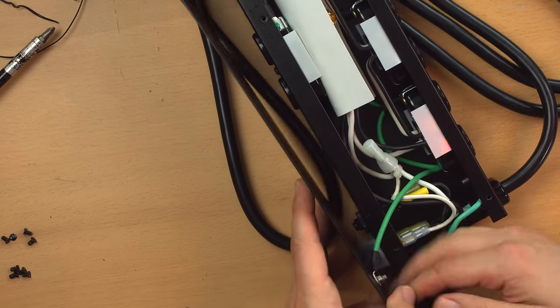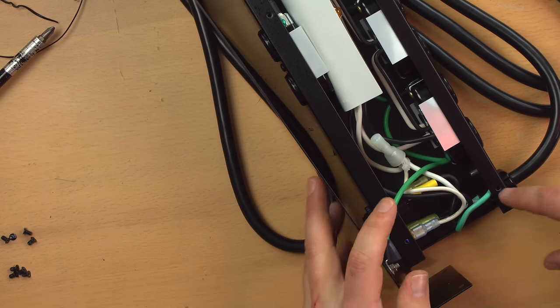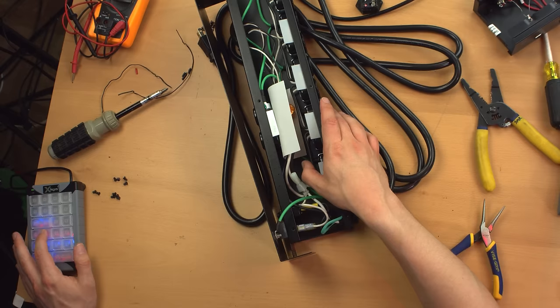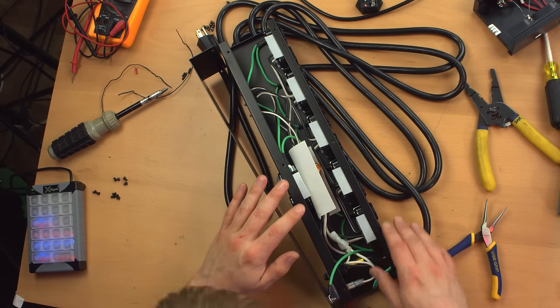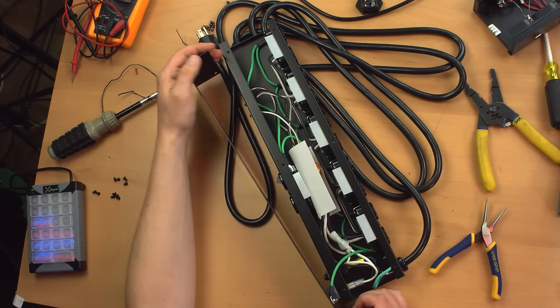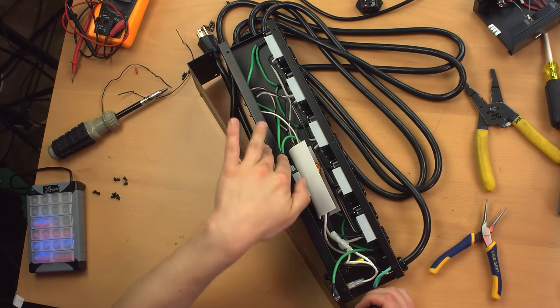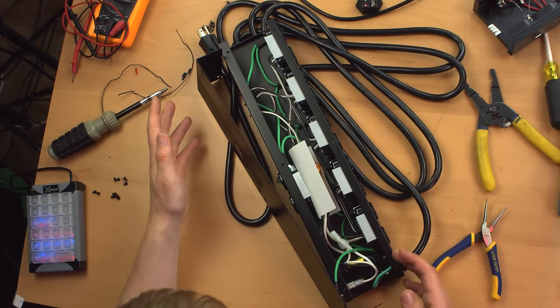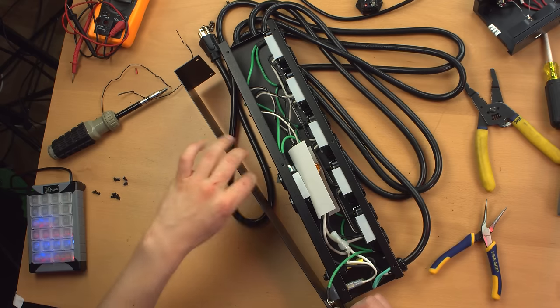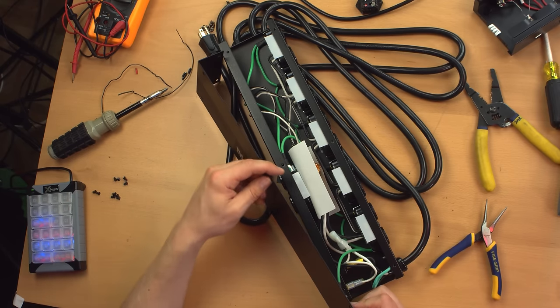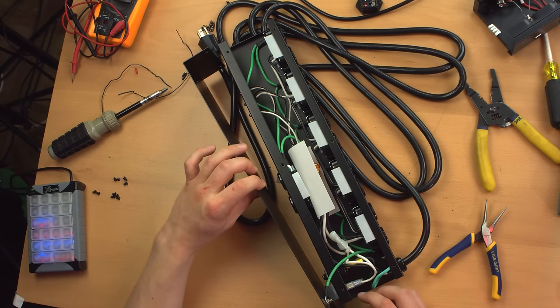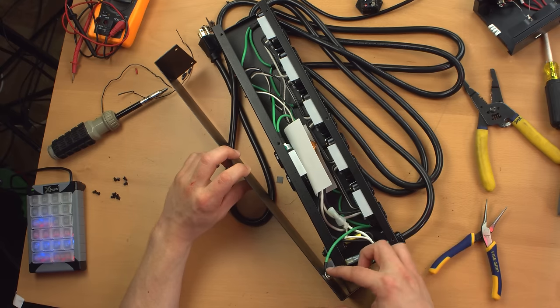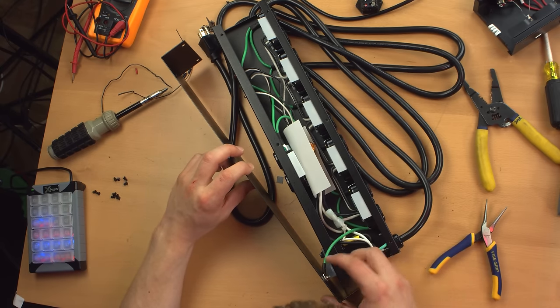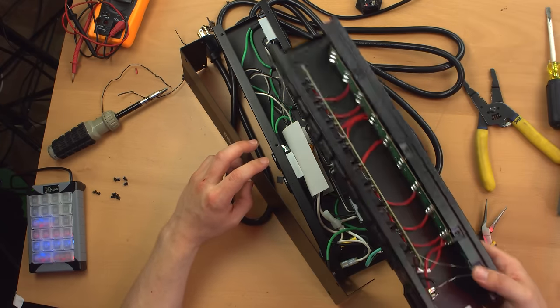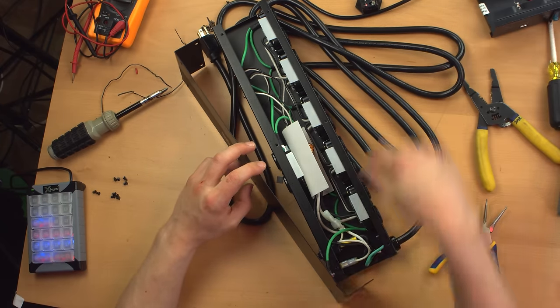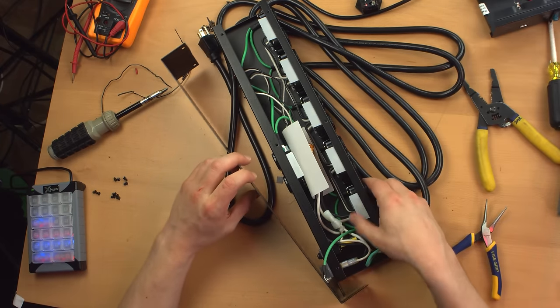and then it has a separate connection to the top of the chassis, even though in any reasonable circumstance, this would probably end up being adequately bonded just by virtue of the screws connecting them. I mean, it's enameled metal, but the screws are going to tear into the enamel a little bit, but you don't want to rely on that. That would just be bad practice. So the fact that they have this extra bonding wire to the top plate, which incidentally this does not have, that's a real touch of class and quality right there.